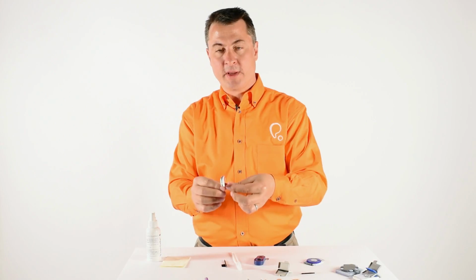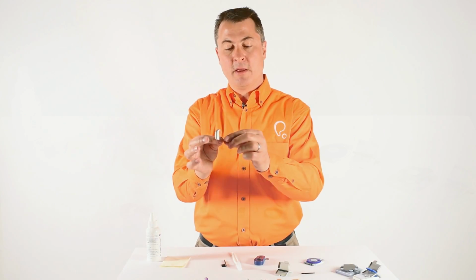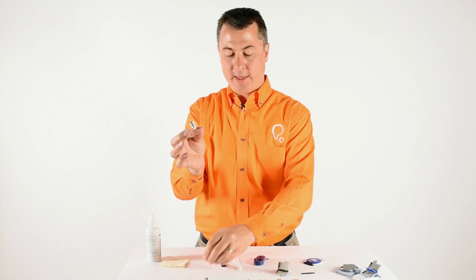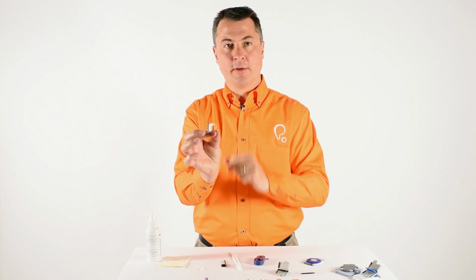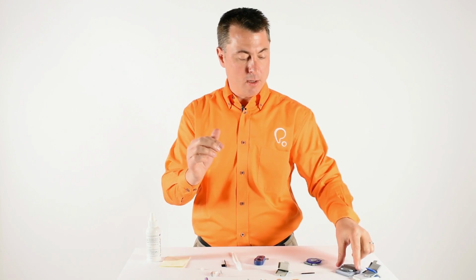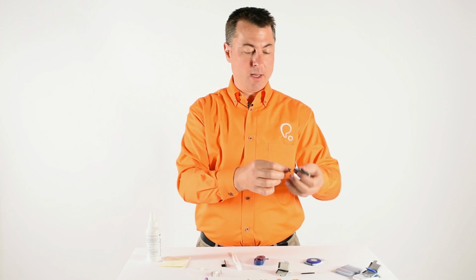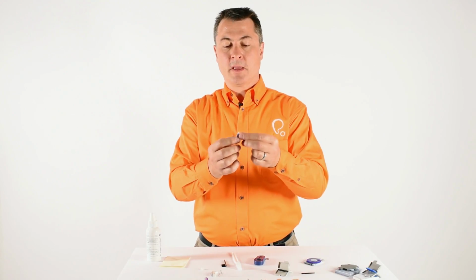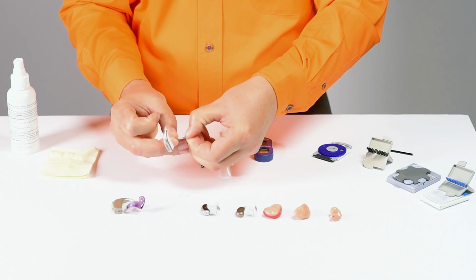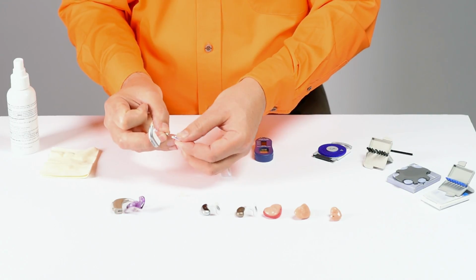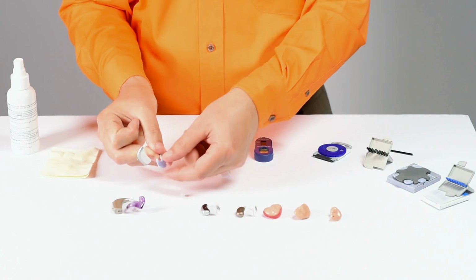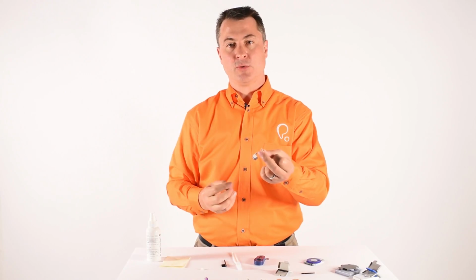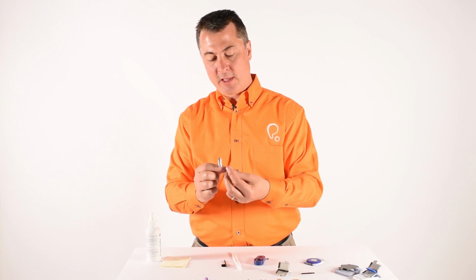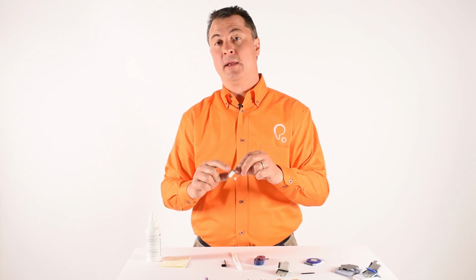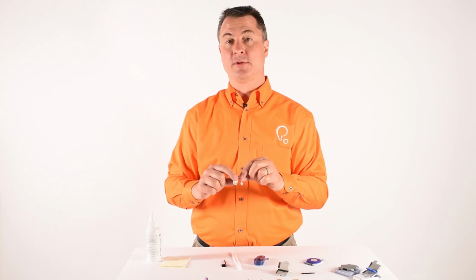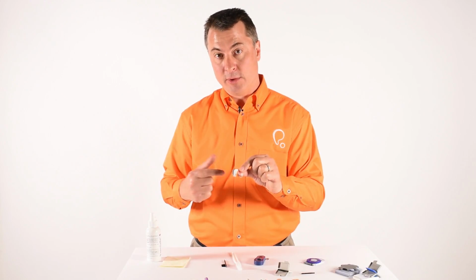Similar over here, in this particular case, this is a different brand. It has a little dome on the end, and I take the dome off, and inside it has another wax guard. This is a different type of wax guard, but again, let me see if I can get one with a replacement. You can see the little white cup, and then you can see the other side, which is empty. I would take the empty side, push it in, remove the old one, and put the new one in. Ta-da! I have now a clear passageway from the speaker. So as you can see, having wax block the passage to the speaker is a real concern to many hearing aid manufacturers, and they've come up with easy ways to clean them, and that will usually solve your problem.